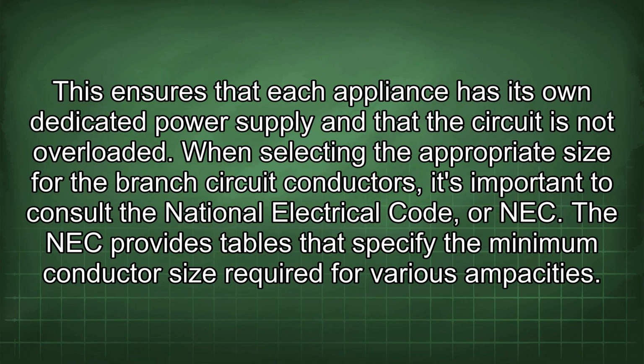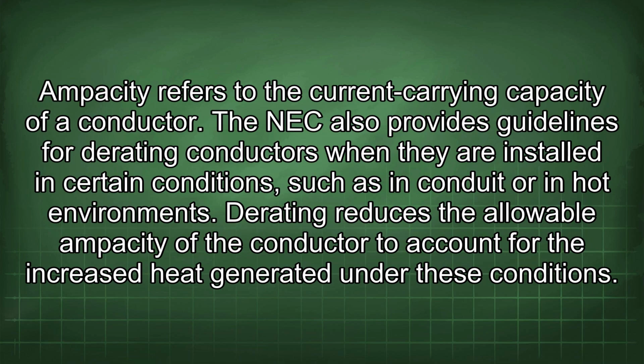When selecting the appropriate size for the branch circuit conductors, it's important to consult the National Electrical Code, or NEC. The NEC provides tables that specify the minimum conductor size required for various ampacities. Ampacity refers to the current carrying capacity of a conductor. The NEC also provides guidelines for derating conductors when they're installed in certain conditions, such as in conduit or in hot environments. Derating reduces the allowable ampacity of the conductor to account for the increased heat generated under these conditions.